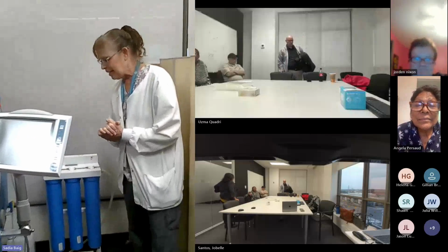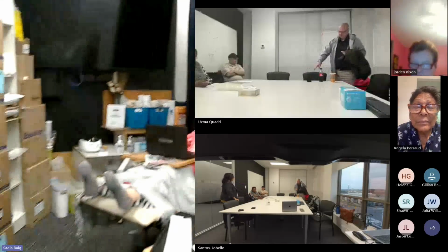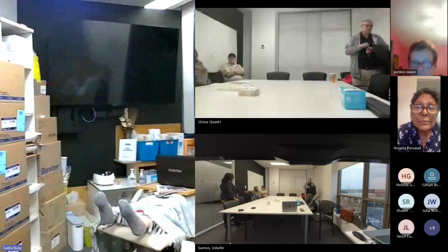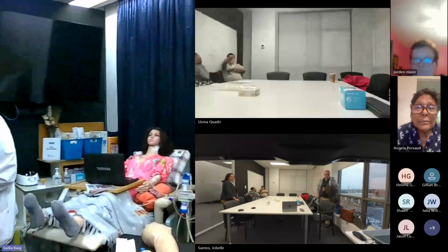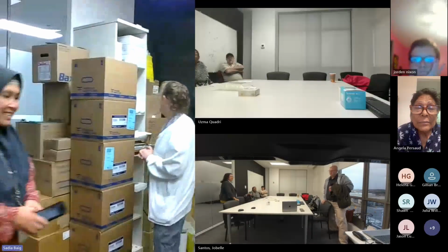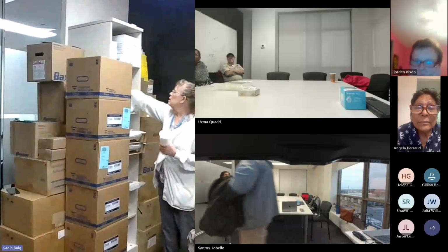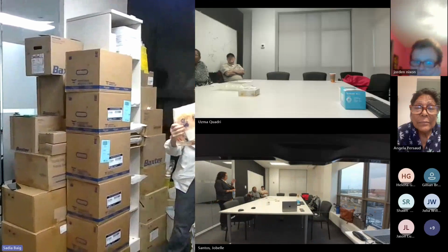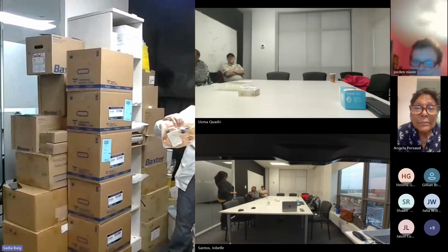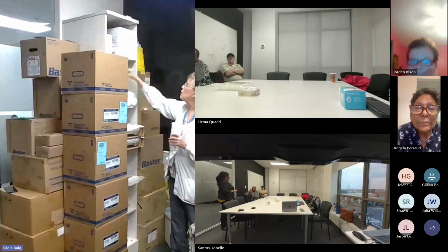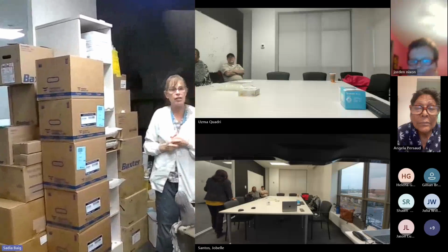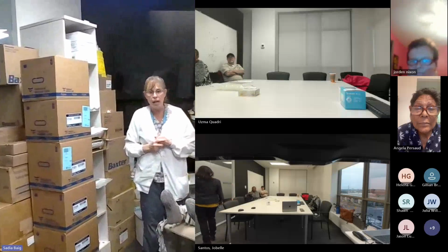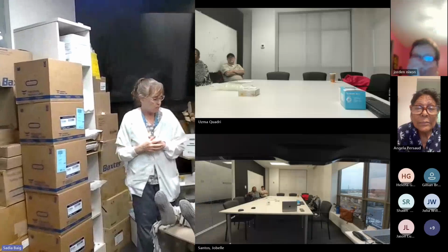And then I want to talk about the supplies. A lot of patients like to have a big screen TV when they're dialyzing. You'll need supplies like dialyzer, tubing, and bicarbonate. And here's what tubing looks like. You'll also need potassium bath and disinfection, because you have to keep your machine clean by doing a disinfection after every treatment and every 2 days.